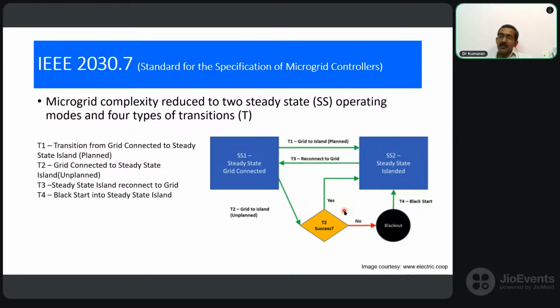If you are depending upon small thermal stations or diesel stations, that's a perfect example, we won't keep these running just to conserve energy, which means we have to perform a cold start. If these DERs are not running at the instant when the transition from grid connected state is required, then we will go for a momentary blackout, and from this blackout we will proceed to what we call a black start.